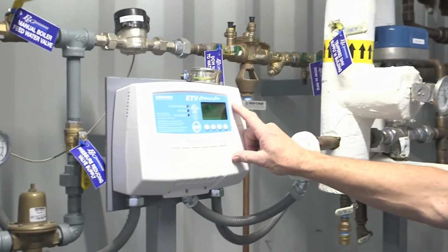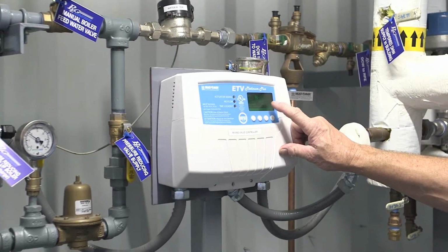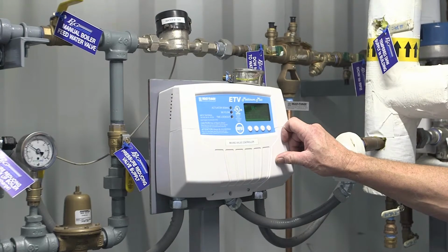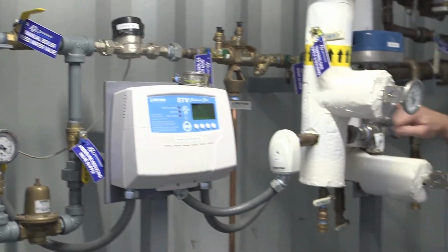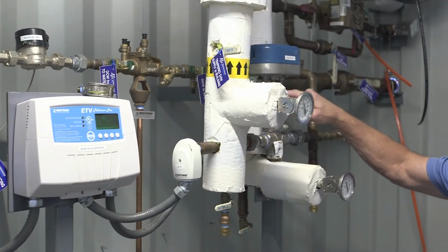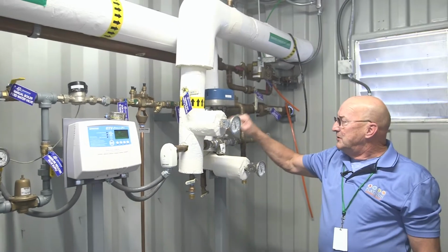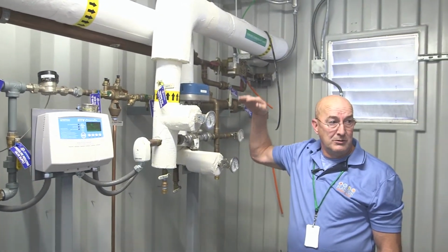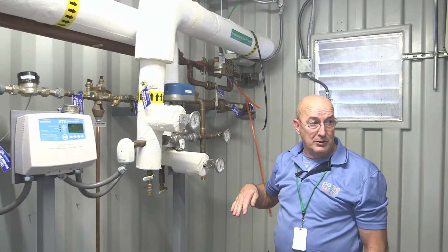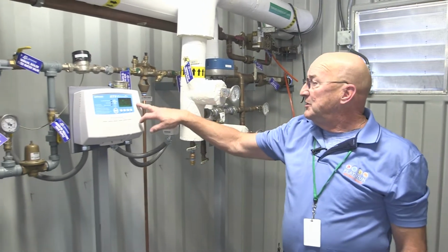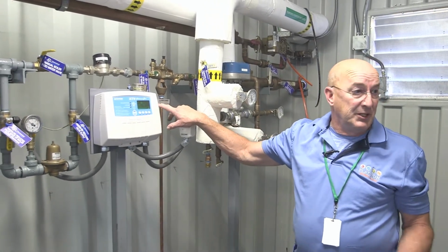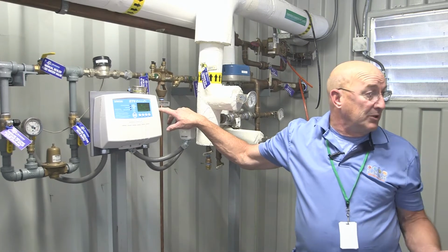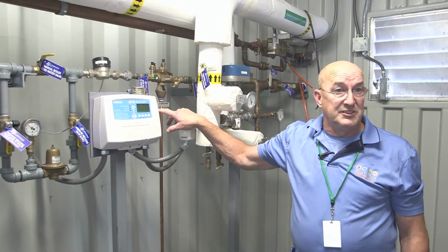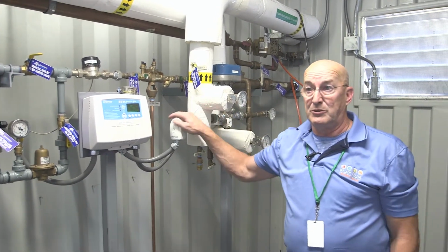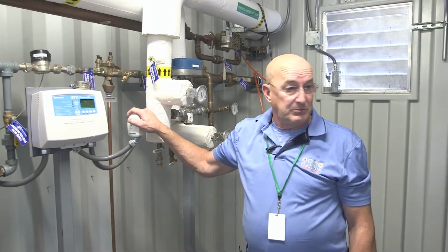Now it's telling you the water is 84 degrees. The target is 120 degrees right now. So it's telling me the valve's all the way up. These two black lines tell you whether the valve is up, all hot water, or down, more cold water. It gives you the instant readout of the temperature. Like you said, we're not showing hot water right now because you're still on the building hot water. Until this is activated, we're sure everything's running correctly, and then we'll activate that.